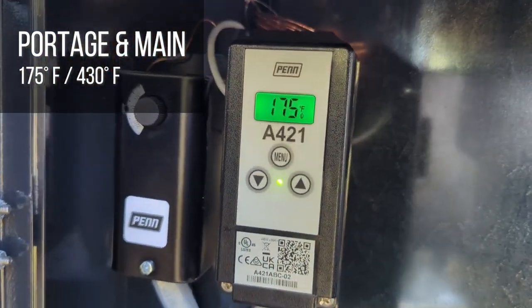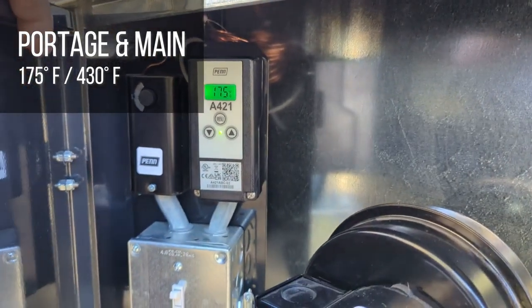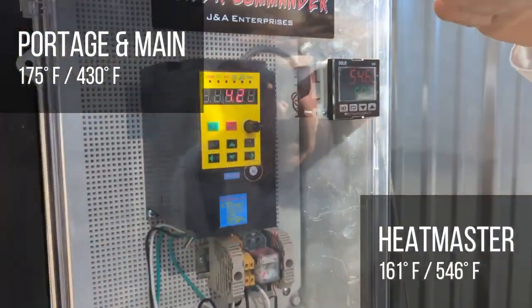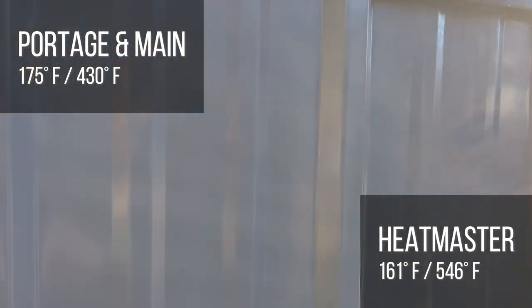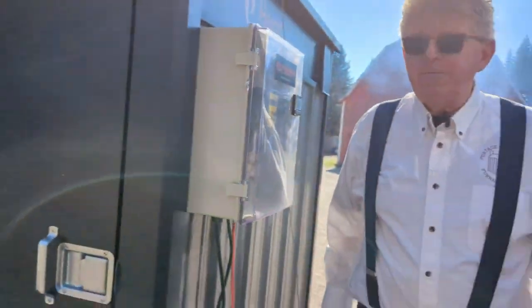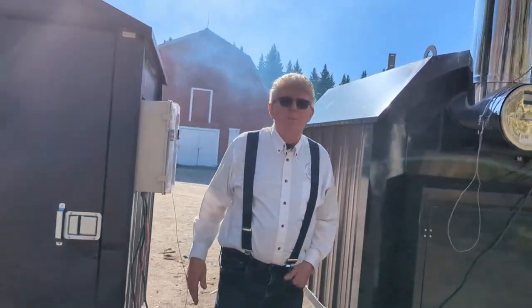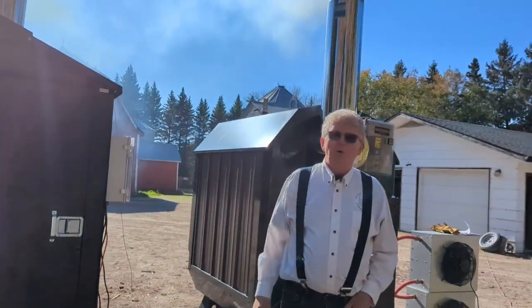The stack temperature on the Portage & Main is 430 degrees Fahrenheit and water temperature is 175 — it's gaining and will likely hit 180 and shut down. Both units are set at 180 degrees. The Heatmaster MF7000 has a stack temperature of 546 degrees and water temperature of only 161 degrees. The backlit display on the Portage & Main Ultimizer 3444 is a nice improvement going from the 419 to the 421 — it's much easier to set and program.